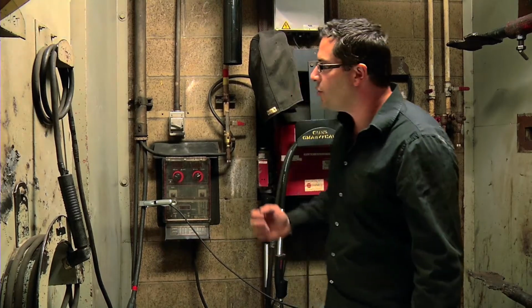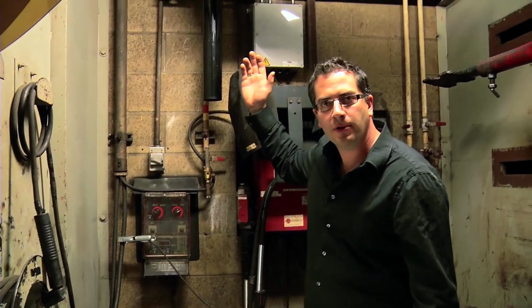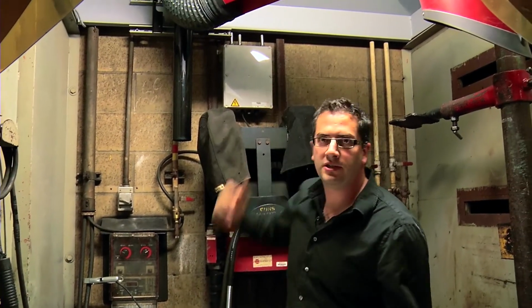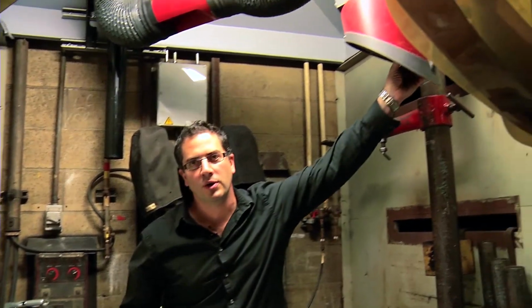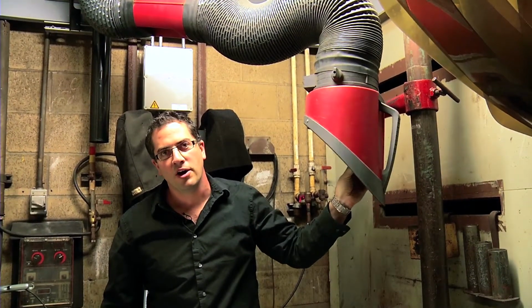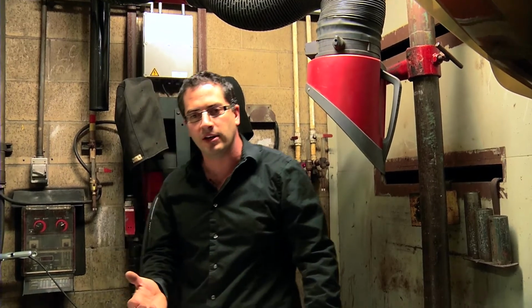What happens is that it opens up the auto dampeners, which allow ventilation to come through the snorkel as you're welding. It has a timer on it. Once it times out and you stop welding, it'll run for about 2 minutes, and then it'll turn off.